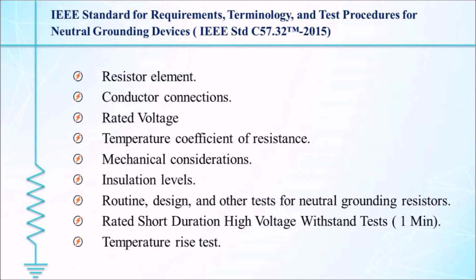The IEEE standards are as follows. We will see them one by one. First, resistor element. A resistor element is the conducting unit which functions to limit the current flow to a predetermined value. The element material shall possess a balanced combination of properties, uniformity of resistance and mechanical stability over the intended operating temperature range without any injurious effect to the elements and their associated insulations.